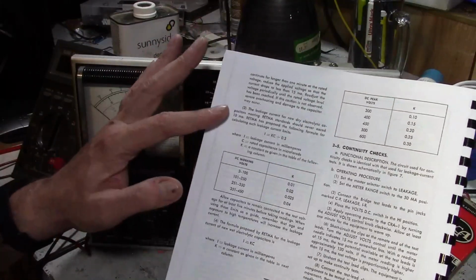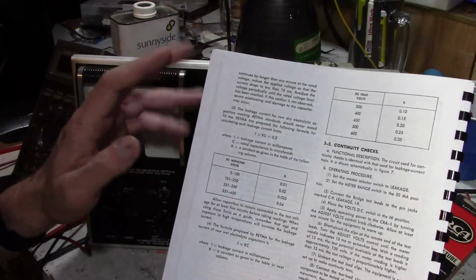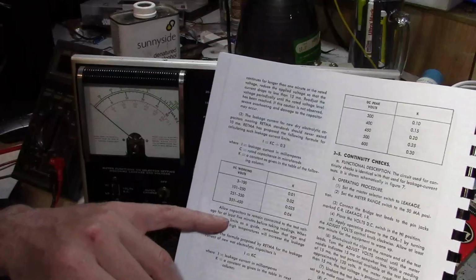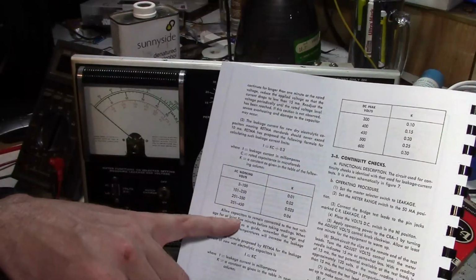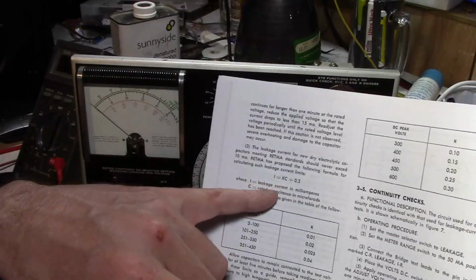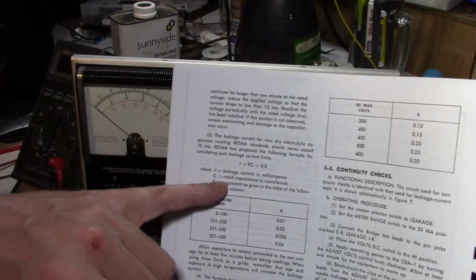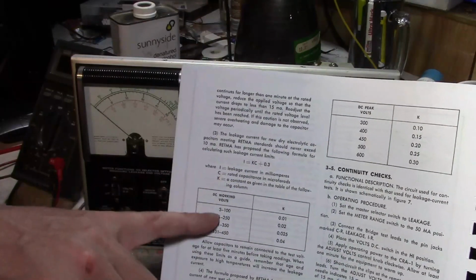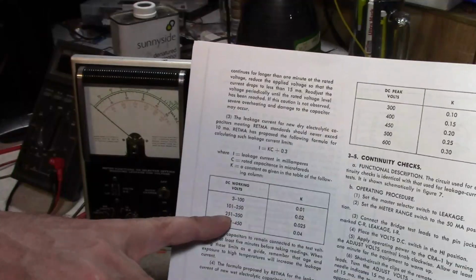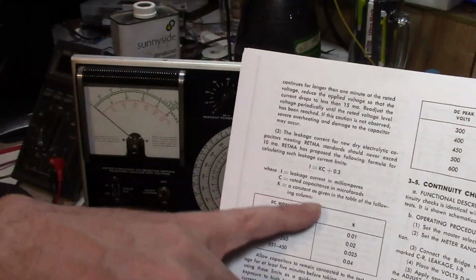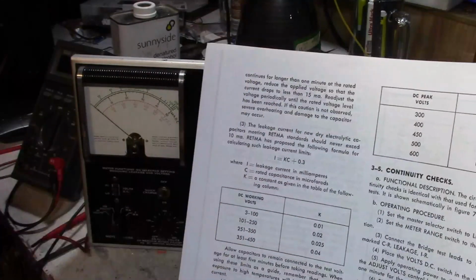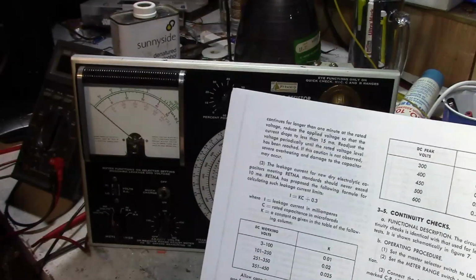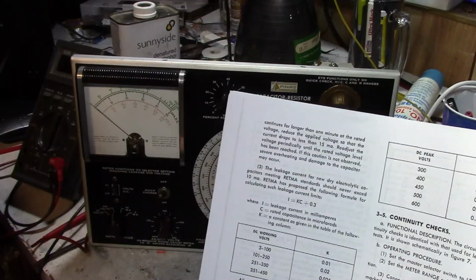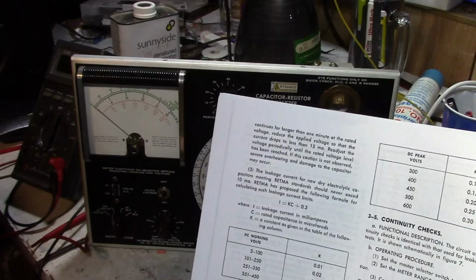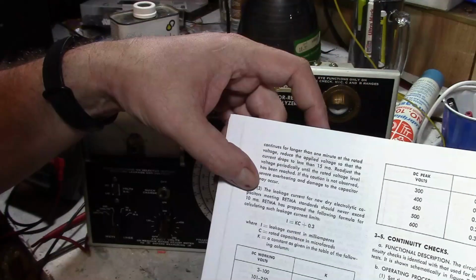There's a lot in here about what's the acceptable tolerance for different types of caps and what's the acceptable leakage. So here, they got a little formula for leakage current in milliamps, rated capacitance, and then depending on what the rated voltage is, you can kind of guesstimate what the acceptable leakage current is for the RETMA standards. They do say it should never exceed 10 milliamps.